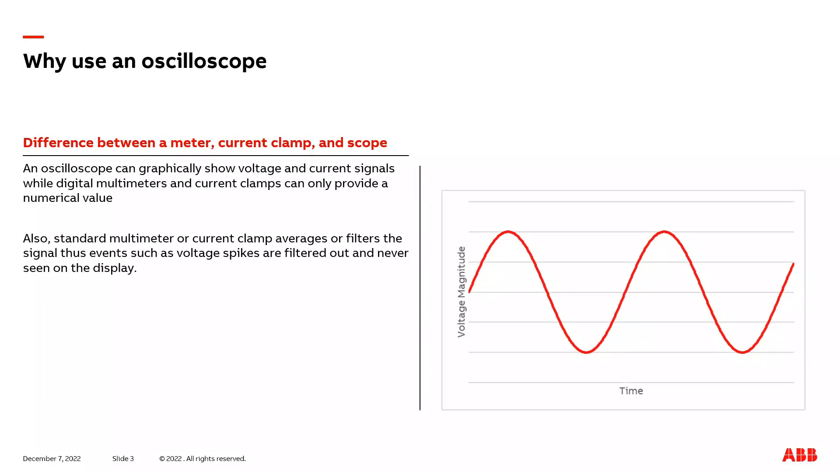So what do we want to use an oscilloscope instead of a basic multimeter or current clamp when trying to troubleshoot issues with a variable frequency drive? The great benefit an oscilloscope has over a basic multimeter or current clamp is that a scope can actually graphically show you the voltage or current signal. A multimeter or current clamp is just going to show you a numerical value only, and the basic meter or current clamp is only going to show you an average value also. You will not see potential transient events that could be occurring on the voltage or current signal.